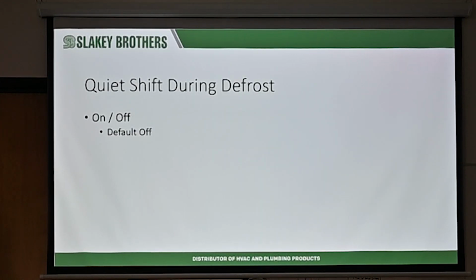Quiet shift and defrost, all that's for is, you guys know what a reverse sound sounds like. That whoosh, swishing sound. If that condenser is right next to the king and queen's house, bedroom, and it's loud and it's obnoxious for them, first of all, they should have paid you to move the unit anyways. But you can do what's called quiet shift. So instead of hearing a big old swish, it shuts the unit off for a little bit. It lets the pressures start to equalize a little more, and then it switches and goes in air conditioning mode to do the defrost. So that swishing sound is softer, it's quieter. Okay? If you run across that, that's what the quiet shift is for.